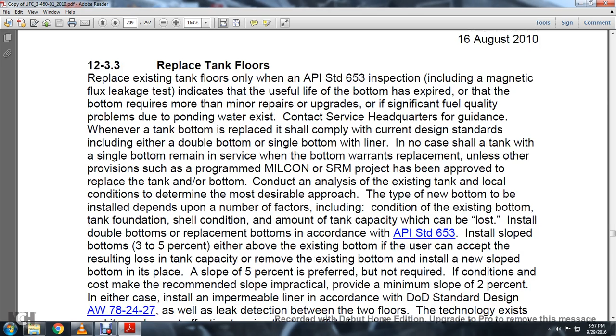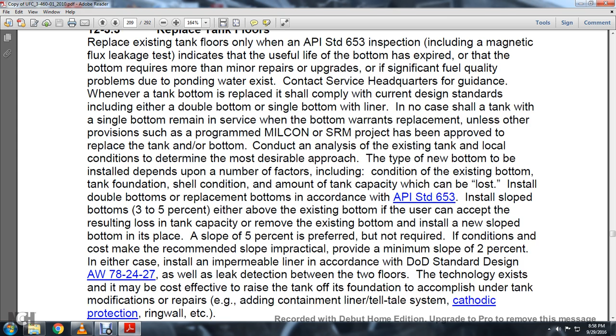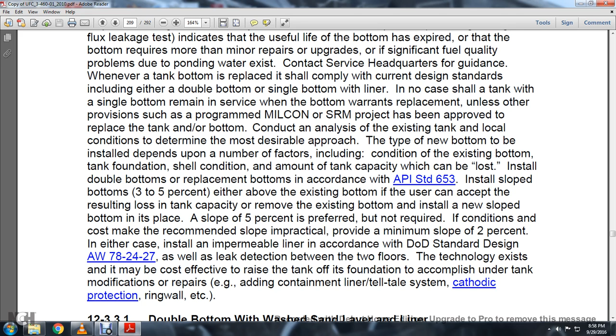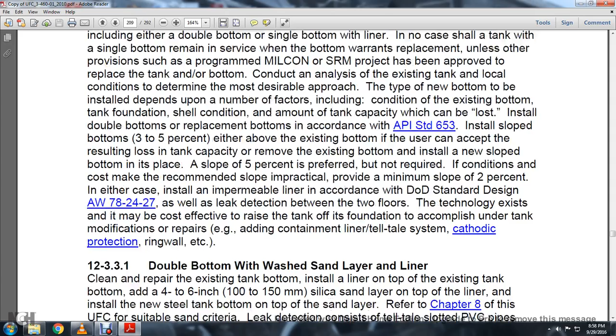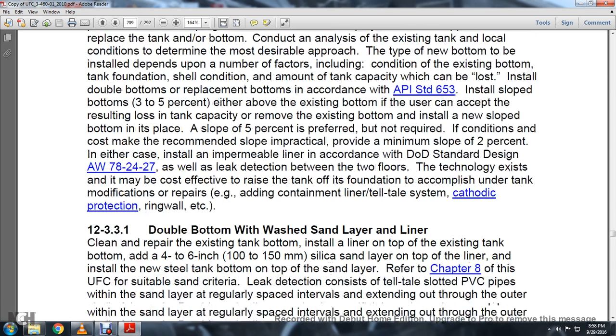In either case, install an impermeable liner in accordance with Department of Defense standard design AW 78-24-27, as well as leak detection between the old and new floors. If technology exists that makes it cost effective to raise the tank and foundation to undertake modifications, make repairs, add a containment inner liner and telltale system, cathodic protection, ring wall, etc.